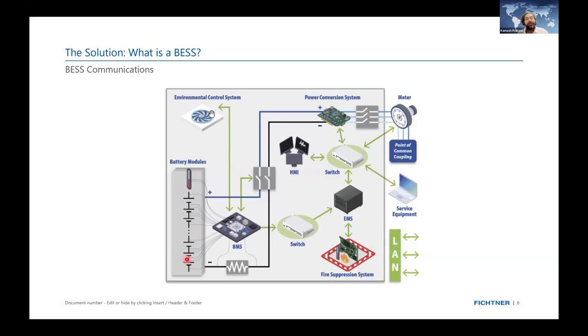If there is a thermal runaway or thermal propagation, those signals are given to the fire suppression system, which works in parallel and autonomous to the main controller. Irrespective of all these, if a thermal runaway is indicated either by gas or by excess temperature, this system will function, and once it functions, it will give a command to isolate the BESS system from the grid. So this is how high level communication takes place.